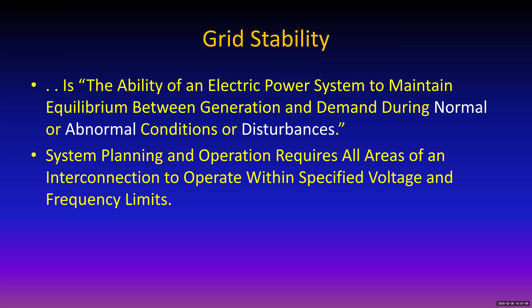Generation and transmission equipment has to operate within normal limits. If you have a rotating machine, it takes a while to get it up to its rotating speed, whether 1800 RPMs or 1200 RPMs. And it has to be not just that number of RPMs, but the phase has to be exactly even with what's out there in the grid before you turn it on. Otherwise you get a big jolt with the thing trying to lock in to be synchronized. That's why it takes a while to get things going again once you lose some generation—getting the rest of the generation synchronized. Now that's with rotating generators.